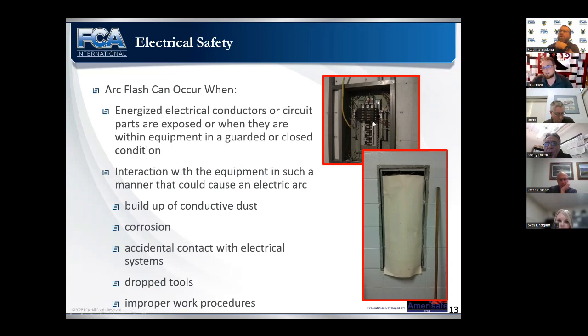Really, whenever we interact with any piece of equipment that has what they call exposed bus, which is on the back side of this panel, right? Whenever you have a bunch of wires going into a panel like this, there is exposed bus. And there's lots of different things that can cause that fault, right? But mostly what it comes down to is dropped tools, or say if you were spraying and it was a flammable material. Fire is plasma, which conducts electricity. So if it gets into here, it can cause an arc, which will cause a spark, which will then travel across phases and create an arc flash. Right. So we need to make sure that we're aware of that and that we train our employees.